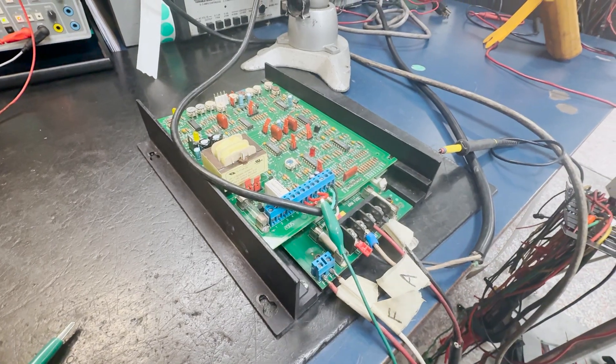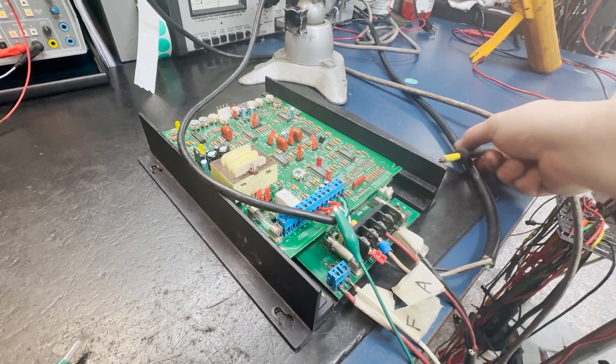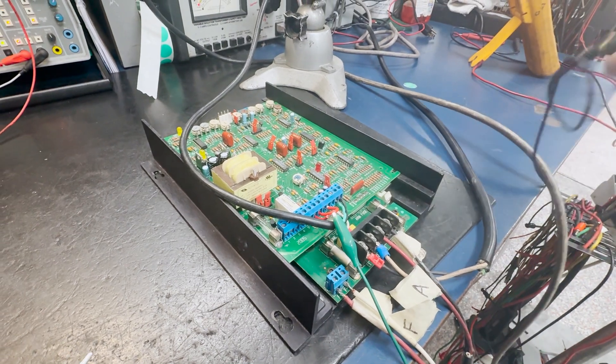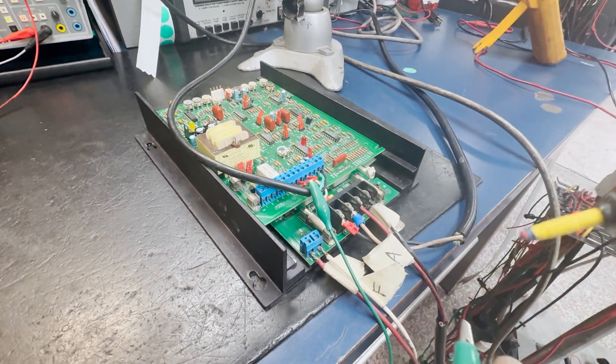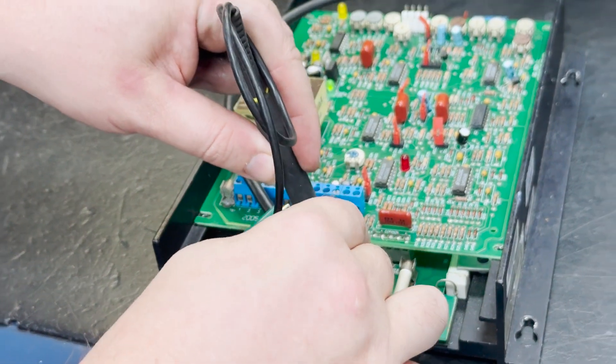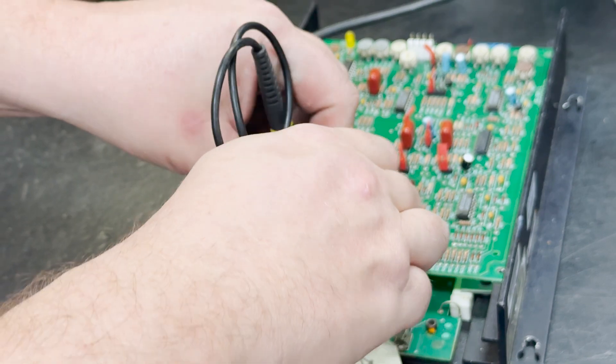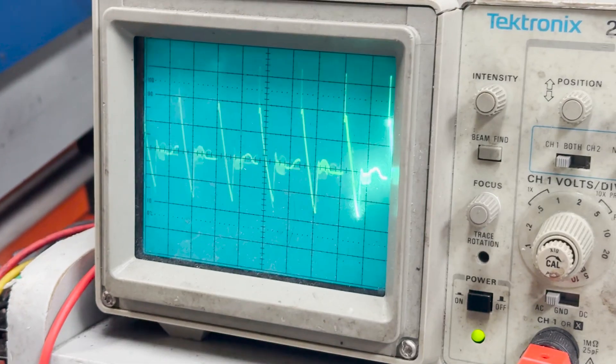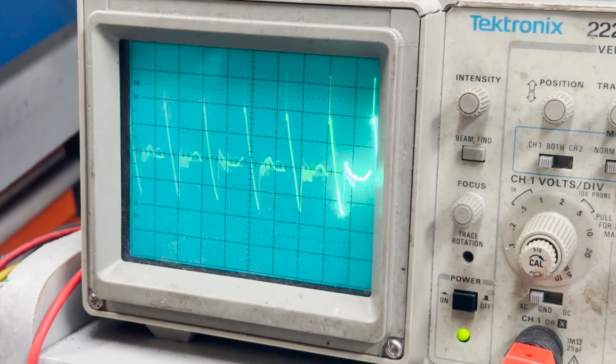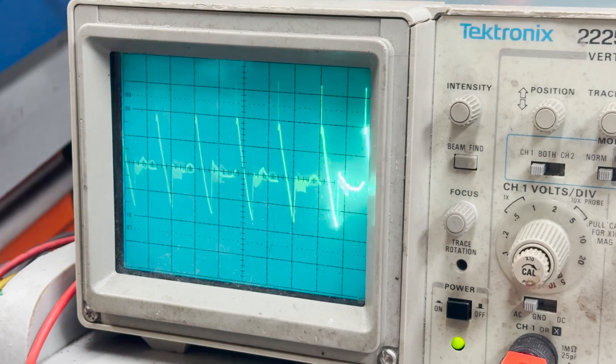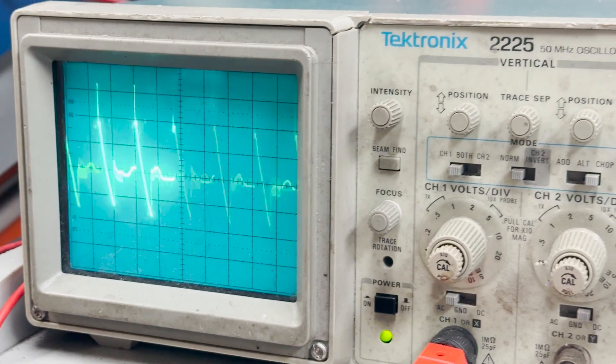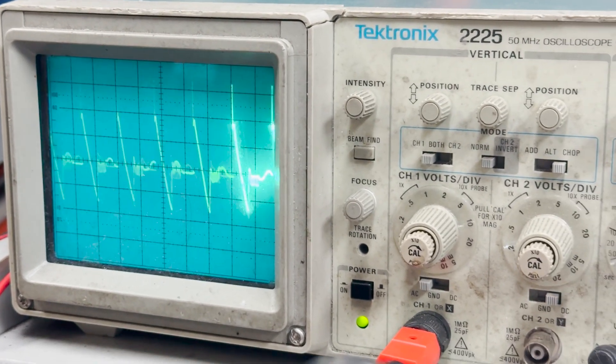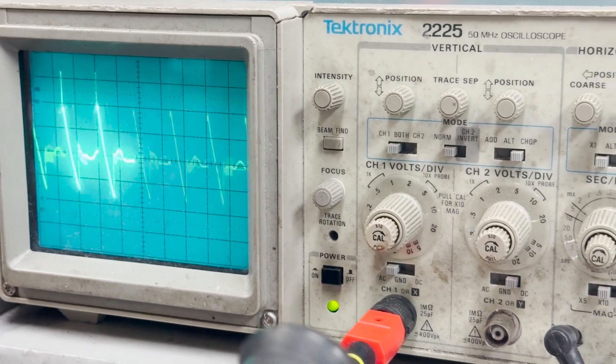We will monitor the output of the drive by using our oscilloscope. I will put my oscilloscope leads here. And now we can see the waveform on the oscilloscope. As we change speeds, we can see changes in the waveform. We have determined that the output of this drive is performing as expected.